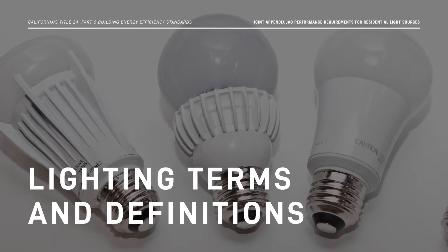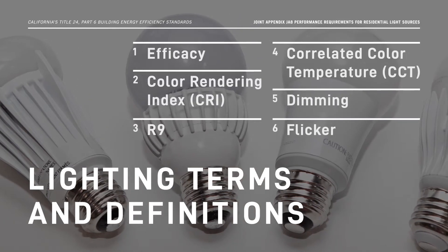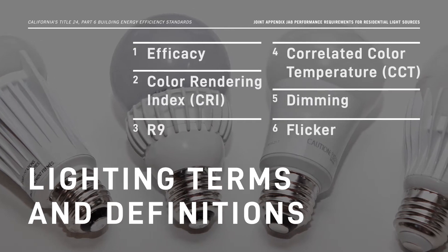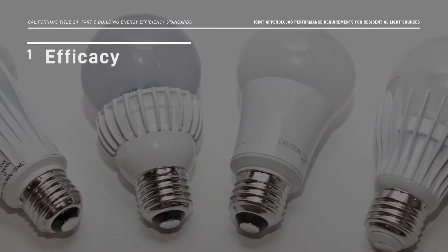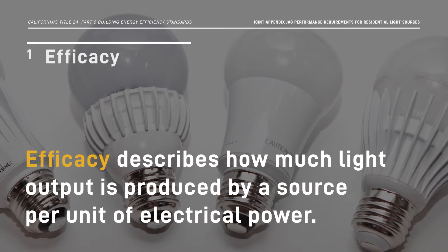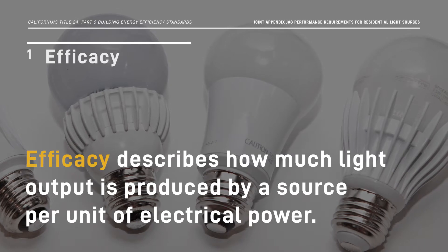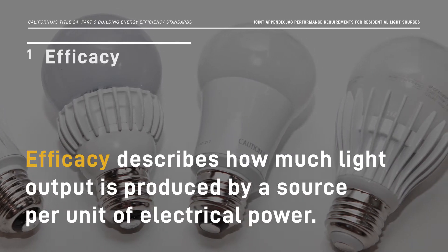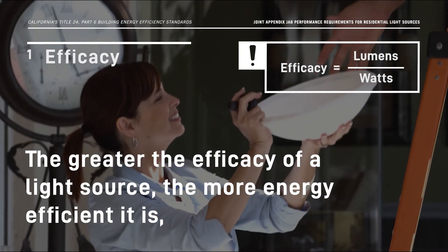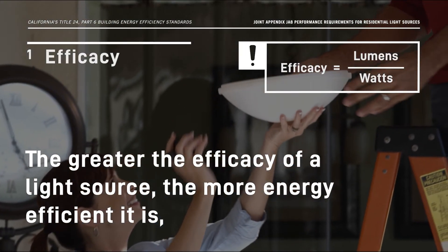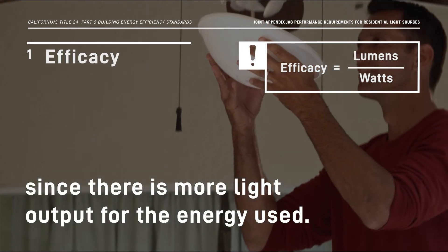Now that we know which light sources must be JA8 certified, let's go over a few lighting terms so you can better understand the requirements. First, let's define efficacy. Efficacy describes how much light output is produced by a source per unit of electrical power. It is measured in lumens per watt. The greater the efficacy of a light source, the more energy-efficient it is, since there is more light output for the energy used.